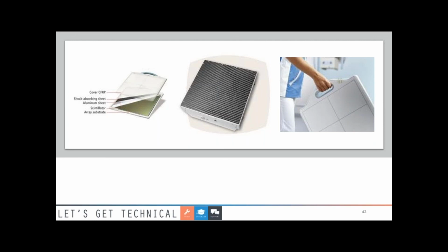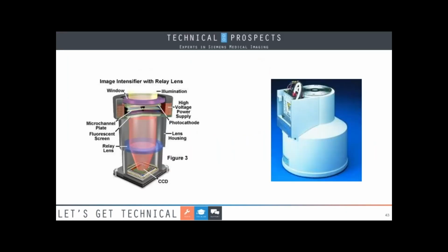And the others you have, and most of these are, this is an analog system with an image intensifier. And a lot of those will also be older, will use film. Film's kind of still around there, as are cassettes, but luckily they're kind of a dummy, because detectors, while they're really expensive, about $105,000 for a detector, they're very reliable and very easy to deal with. If you got film, you got to go to their little cabinet and you got to get that, and then they got to process it and everything.